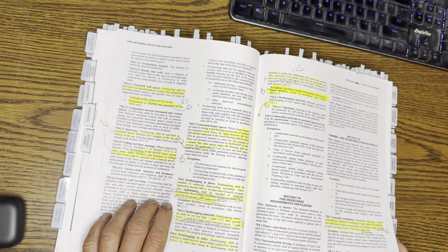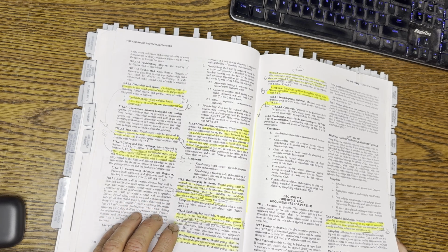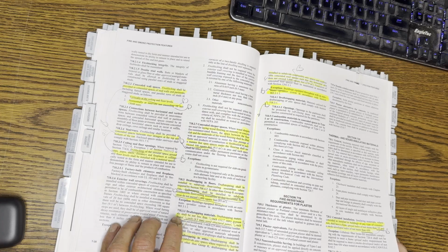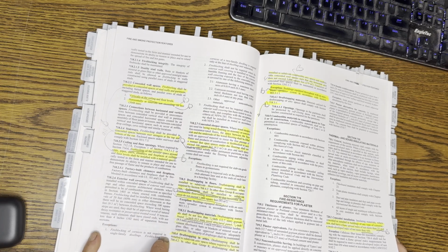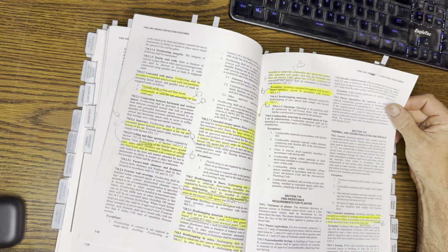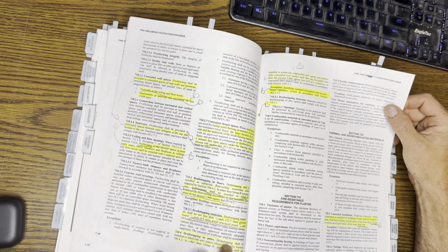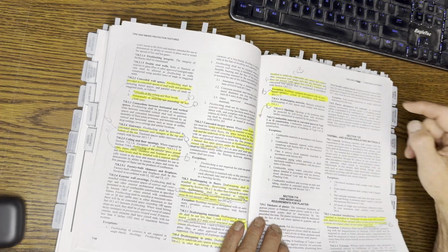Note the 1,000 square feet for draft stopping. Know what you can use for draft stopping materials. You can use 3/8 inch wood panels. And 3,000 square feet for an attic is kind of a magic number. Draft stopping in attics, every 3,000 square feet you have to be draft stopped, unless you're equipped with a suppression system.